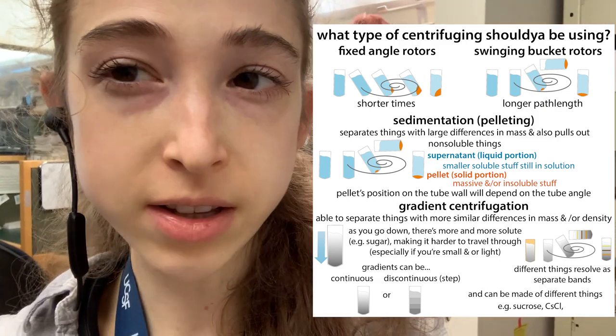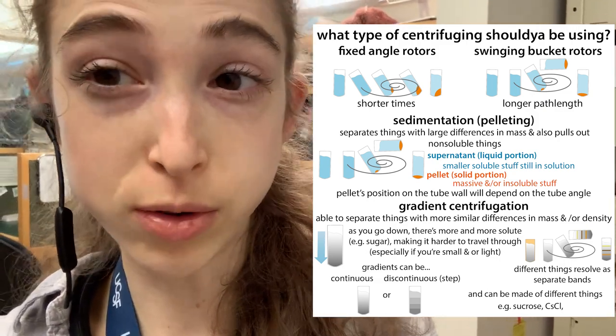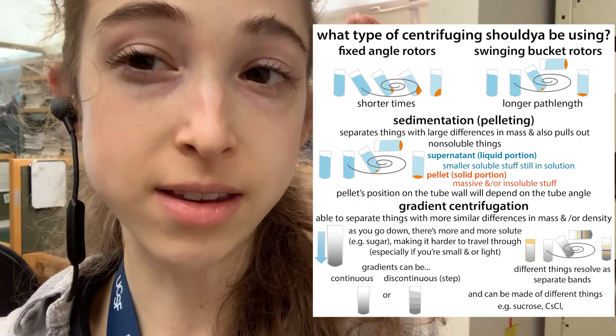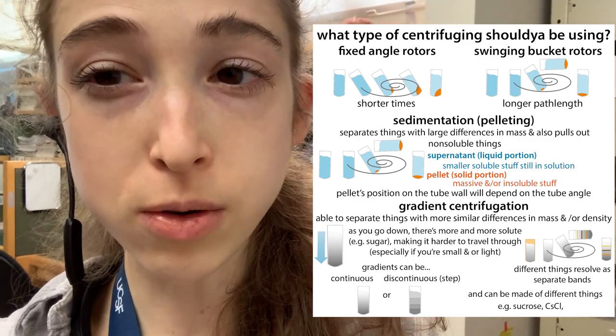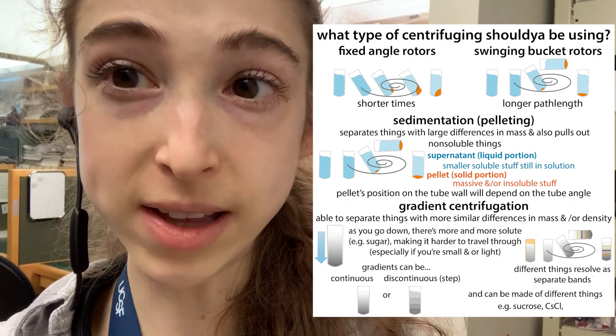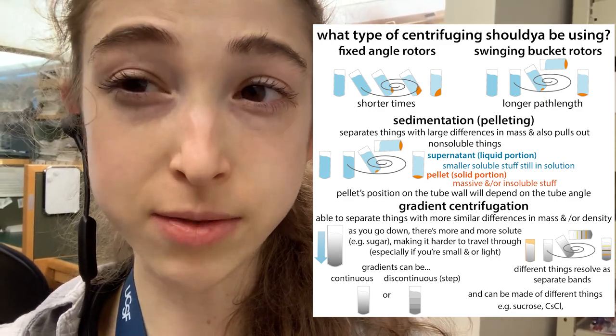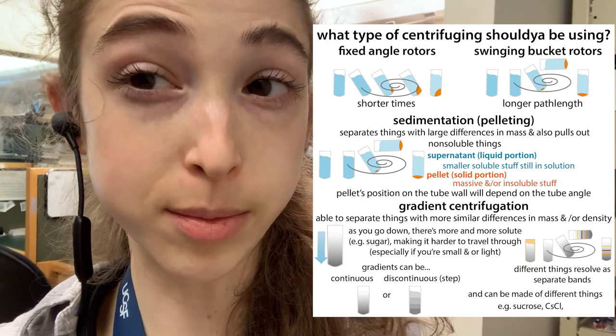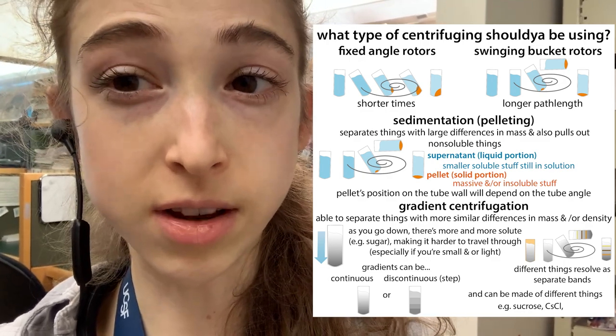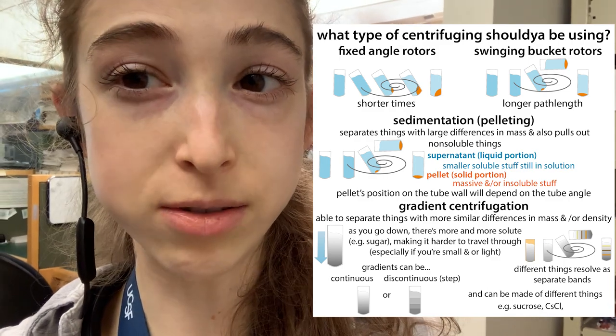Swinging buckets are good for gradients because you get the longest separation distance. When the tube goes horizontal, you travel through the whole tube length, whereas at an angle it's only partial. It's like size exclusion chromatography — the longer your column, the better the separation. The longer your gradient distance, the more you can spread things out.